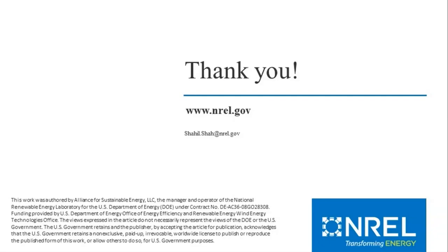Yes, that is a very good question. Impedance is a big function of the control system. So yes, it will be impacted by the control system used in inverter-based resources. And it may not be possible to measure the impedance of wind turbines or big utility-scale inverters in real time. But what we can do is measure that impedance in the laboratory for different operating conditions and identify the worst-case scenario where the impedance is worse in terms of having very low damping or introducing resonant modes.